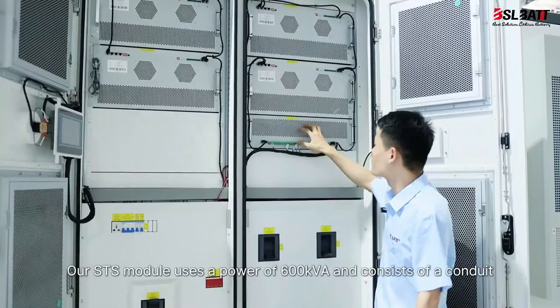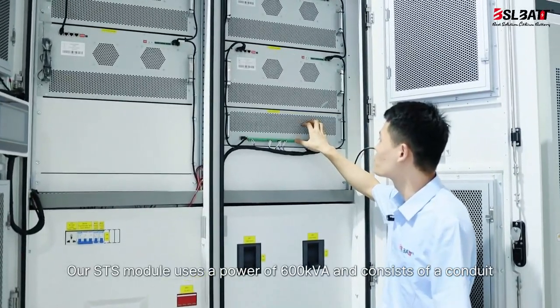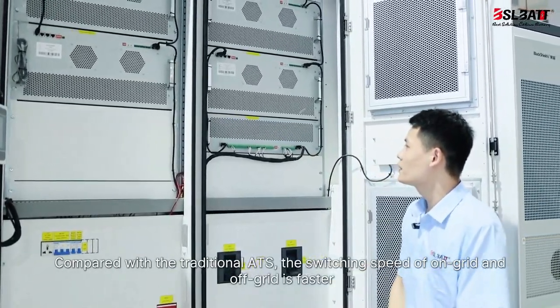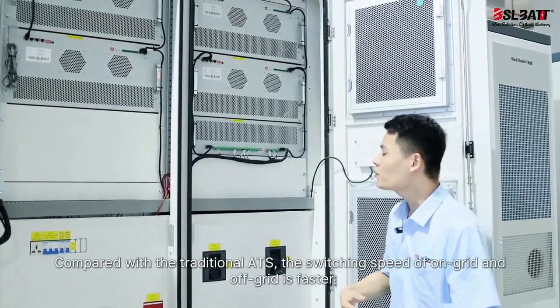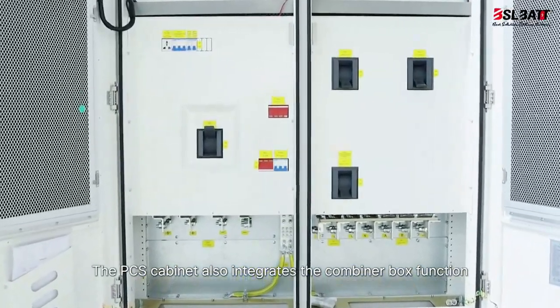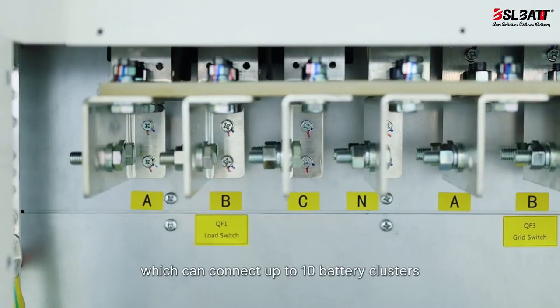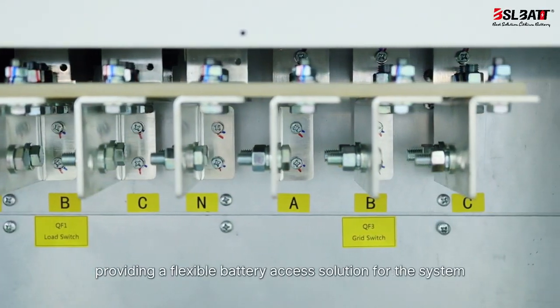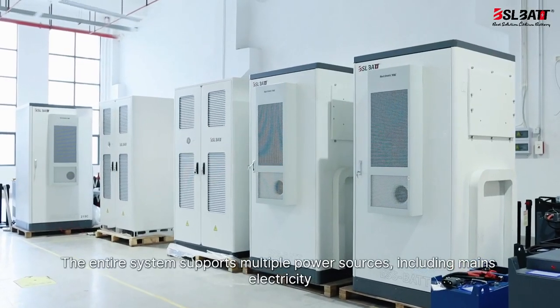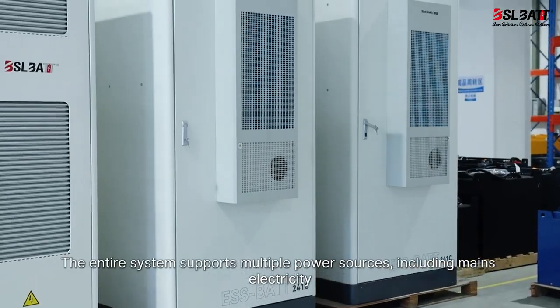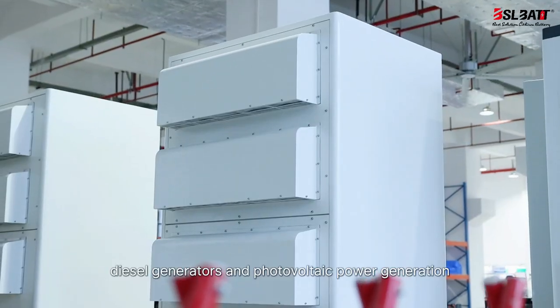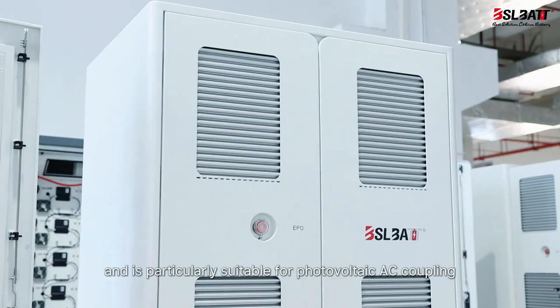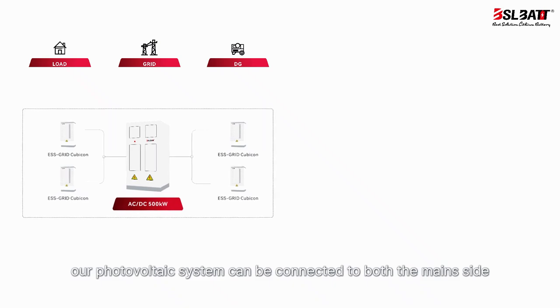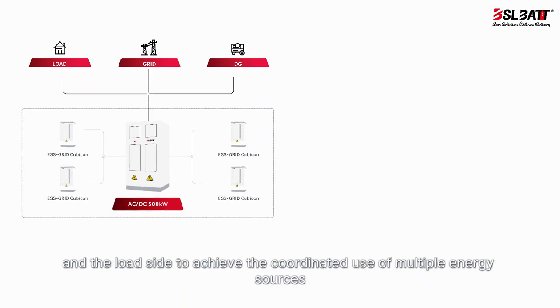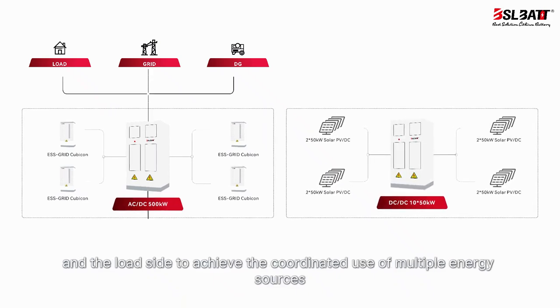Our STS module uses a power of 600 kVA. Compared with the traditional ATS, the switching speed of on-grid and off-grid is faster. The PCS cabinet also integrates the combiner box function, which can connect up to 10 battery clusters, providing a flexible battery access solution for the system. The entire system supports multiple power sources, including mains electricity, diesel generators and photovoltaic power generation, and is particularly suitable for photovoltaic AC coupling. As can be seen from the figure, our photovoltaic system can be connected to both the main side and the load side to achieve the coordinated use of multiple energy sources.